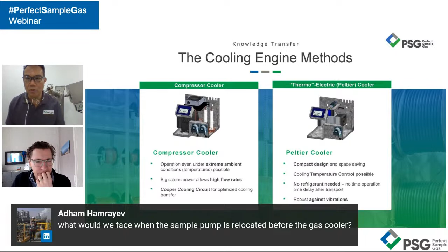The question from Adham was: what would we face if the sample pump is relocated before the gas cooler? In other words, the flow comes from the pump first, then the gas cooler. This is something I strongly discourage, meaning avoid doing so.